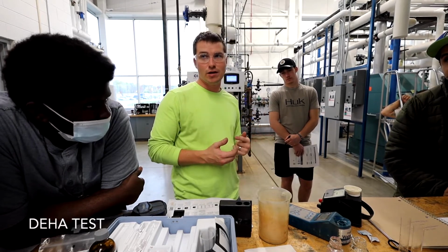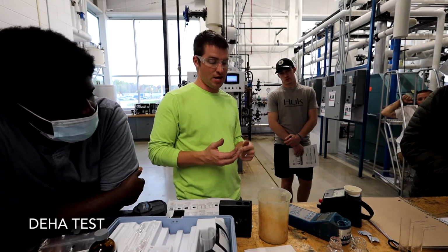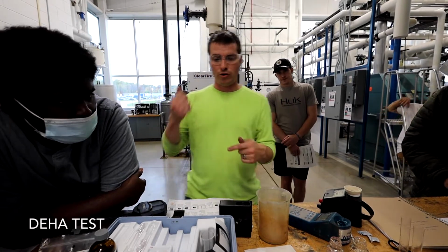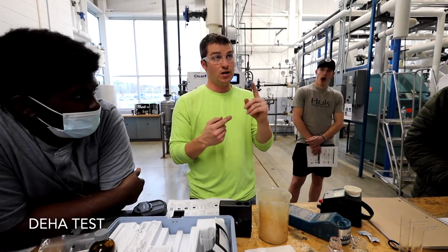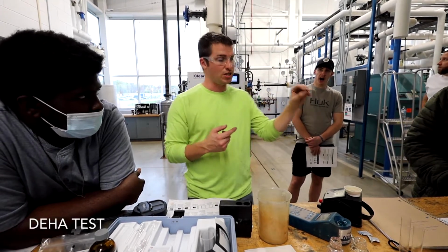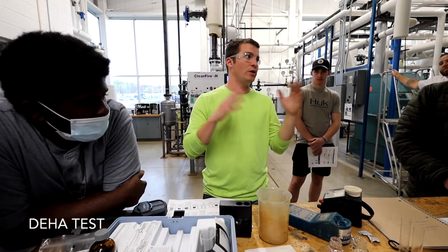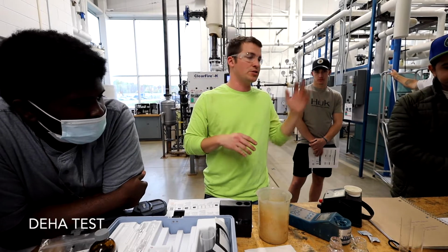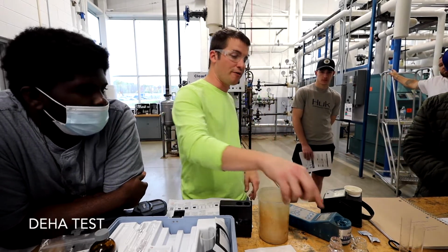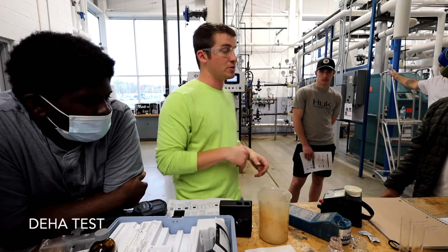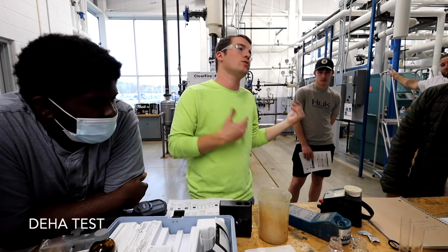The other way, which is how I believe we are doing it here, unless something's changed to my knowledge, is as we add fresh soft water into the feed water tank, there's a water meter that spins. When that water meter spins so many times, it sends a pulse signal over to the little controller on the wall. The controller then says, hey, you need to turn this pump on and run it for a minute or 2 minutes or 30 seconds or whatever. So again, the hard part here is you might find this is going to be low. So I'm probably going to say we just need to turn that pump on and run it to get some in, because you don't really go through water.